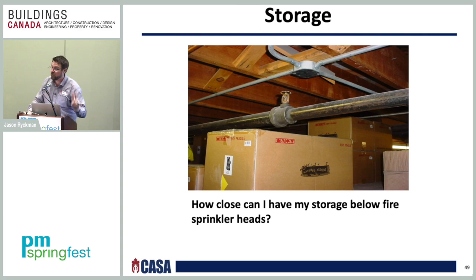If you have special sprinklers, such as ESFRs, CMSAs, ESFRs is early suppression fast response. CMSAs is control mode specific application, which those are storage type of sprinkler heads. You need 36 inches, not 18 inches. And the reason for that is the development of the sprinkler stream. So the stream itself, it needs that space for a proper sprinkler spray. Also too, any secured type of obstruction that is wider than 4 feet, it would also need a sprinkler head underneath it. And that's basically for any installation type of, that should be under there during installation.